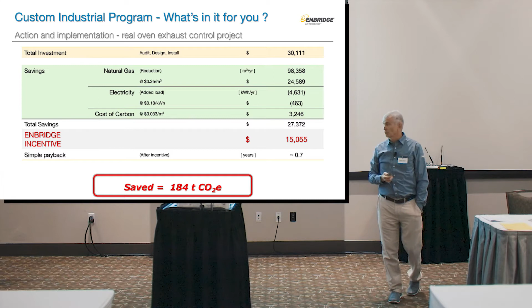So these guys actually save by investing $30,000 in a heat exchanger, 2 VFDs, an additional fan, all the ducting, and saved 100,000 cubic meters of natural gas. In this case, because they installed an additional fan, they use 4,000 kilowatt hours more of electricity, but it still gets them to about a 0.7-year payback with our incentive. And in this case, the incentive was exactly half of the cost of the project because they maxed out. So for a $15,000 investment on their part, they are saving 100,000 cubic meters every year, which ends up being about 184 tons of CO2 equivalent.